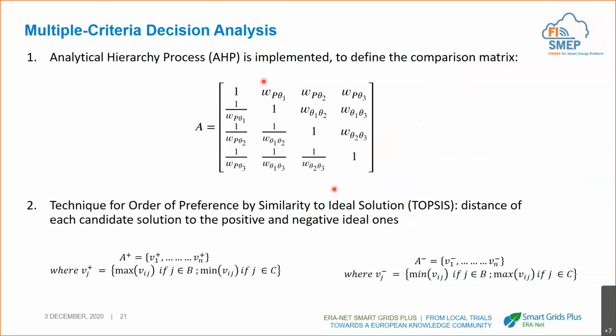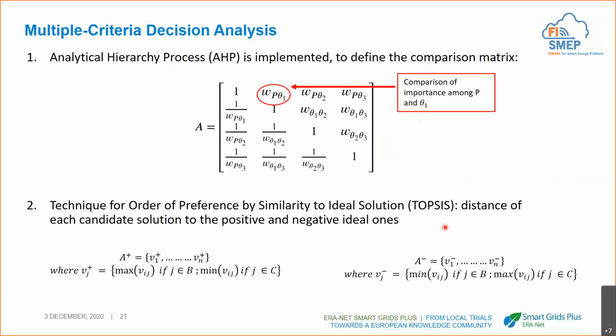So in this matrix, for example, here, we compare P and theta 1. Here we will compare P and theta 2, and so on. And the grid operator will assign an importance which is more important among P and theta 1. In this way, we pass from the comparison among 4 criteria to the comparison among 2 criteria, which is easier to be faced. And the second part, which is the TOPSIS, defines which is the ideally good solution and the ideally negative solution, and measure each candidate from these 2 positive and negative ideally solutions. So the best one, the solution that is closer to the positive one, it is chosen for the final implementation.